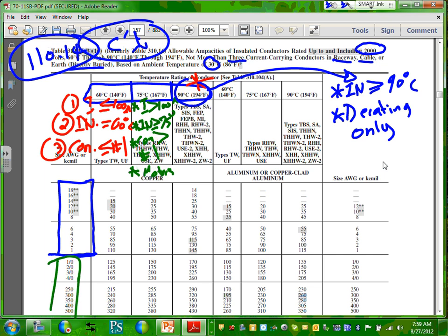Now you work for Excel, young fella, right? You're an exception. For medium voltage, we size, our starting sizing is based on the 90-degree column. Only for medium voltage, higher than 600 volt. Now, most of you, probably 90% of the time, you're going to be working with less than 600 volt. So these rules will apply to you.